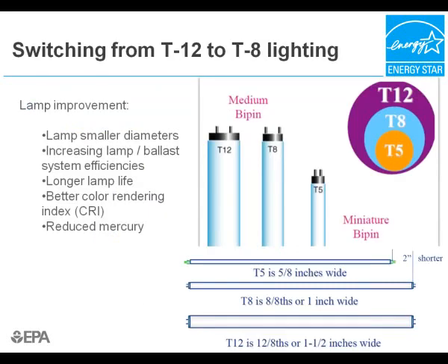What is wrong with T12 lighting? First, T12s are an old and inefficient technology. It is an energy hog. Replacing it with T8 fluorescent systems can save up to 40% in lighting energy costs. It is expensive to run. Upgrading to a T8 system usually pays for itself in less than 3 years.